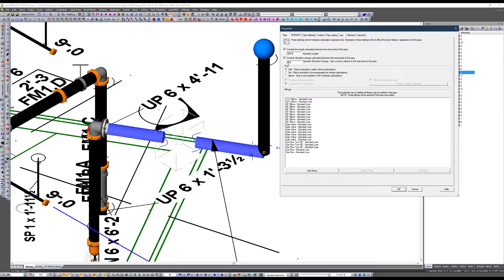Positive six feet means gaining elevation from start point to end point, so in the hydraulic calculations you would lose pressure for that elevation gain. A negative value — where the pipe slopes downhill — means you'd be gaining pressure in the hydraulic calculations. It's important to include the total distance because the program spreads the elevation loss across that distance, calculating frictional resistance for that length plus any fittings, and then also applies an elevation loss or gain based on this value.